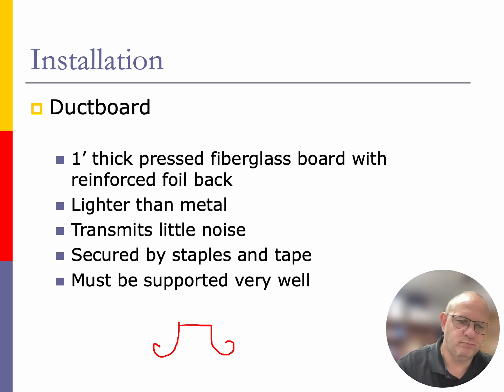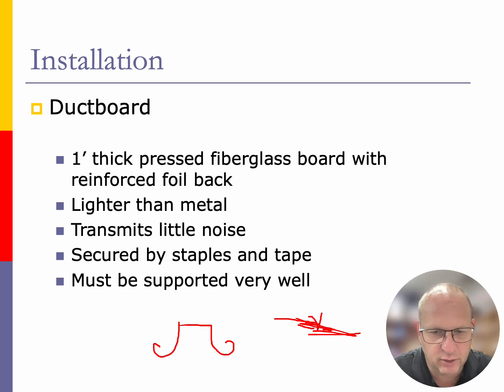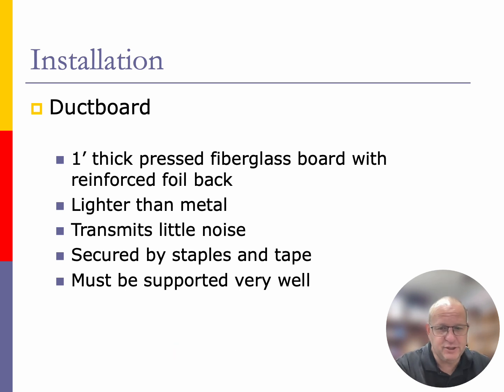We create flaps and grooves that the ductboard will fit inside of the other ductboard, and that flap is going to be taped over top of the other ductboard that's running in this direction, giving it a nice tight air seal, so no need for any mastic or caulk on a brush to seal the air that's coming out of these units. Has to be well supported because it's not as rigid as our metal ductwork. So looking about every 4 feet, supporting this ductwork with some sort of strapping or unistrut to hold up that ductboard on it. Like I said, I am not a big fan of ductboard, but to each his own.